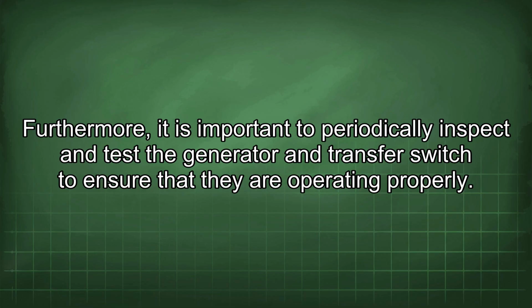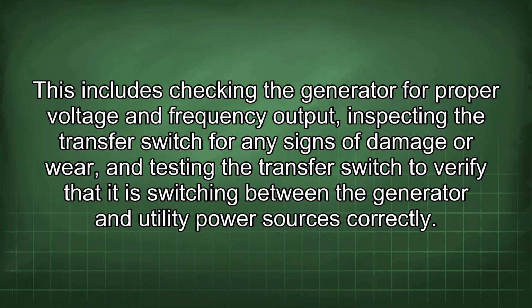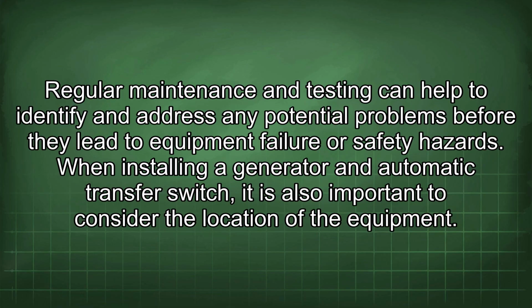Furthermore, it is important to periodically inspect and test the generator and transfer switch to ensure that they are operating properly. This includes checking the generator for proper voltage and frequency output, inspecting the transfer switch for any signs of damage or wear, and testing the transfer switch to verify that it is switching between the generator and utility power sources correctly. Regular maintenance and testing can help to identify and address any potential problems before they lead to equipment failure or safety hazards.